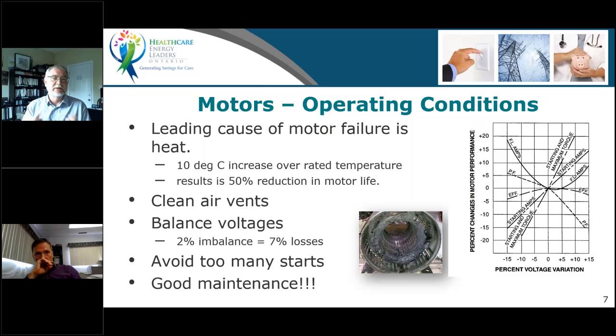And it only takes a 10°C rise over the rated temperature of that motor for it to reduce its life by half. So again, if you've got motors that are failing, you've got to do the post-mortem on them and make sure we understand why. Just replacing with a new motor, and in fact, a new motor may actually be more susceptible to those poor conditions. Even though that new motor might be premium efficiency, it may be more susceptible to the poor conditions than the older motor. So we've got to understand if a motor is failing, if it's overheating, what is it? We've got to fix it, go for root cause, and that will inevitably lead, because heat is not shaft power, to a more efficient motor if we cause it to run cooler.